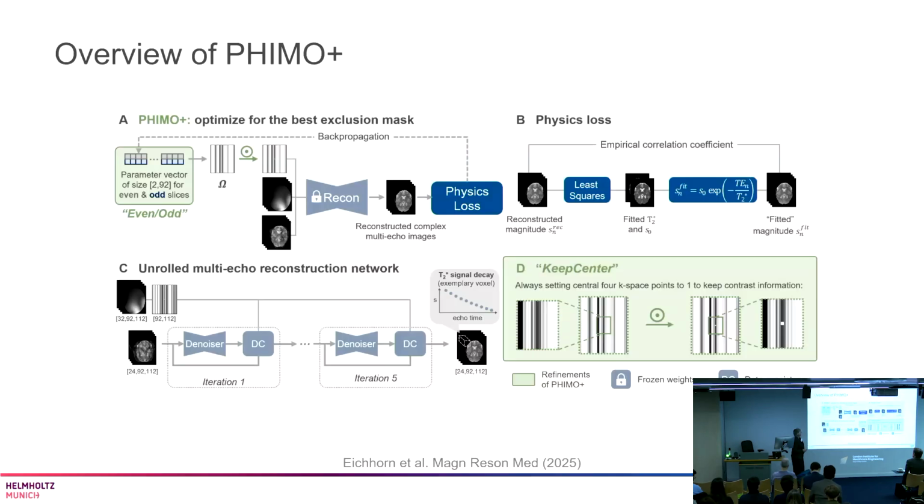Once we've done that, we can run it through any kind of data sets for multi-echo imaging, and it will automatically drop out the lines which will not follow that fit. And then we'll just do a nice multi-echo unrolled reconstruction afterwards, and you get good data.